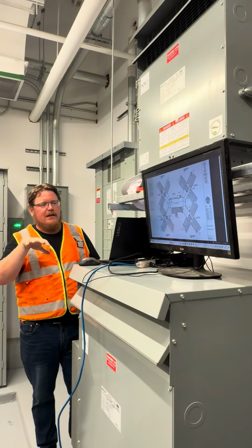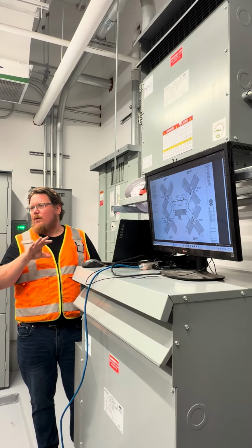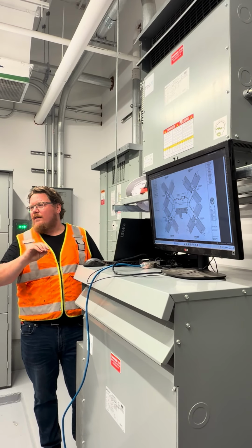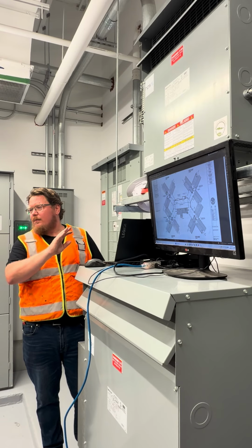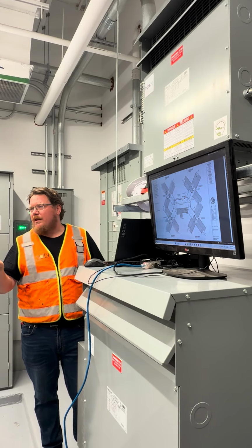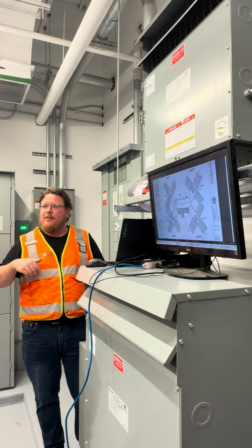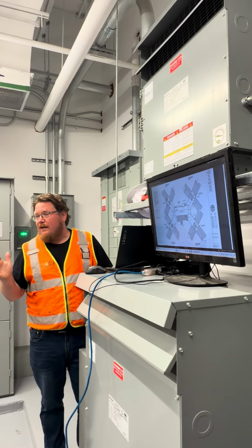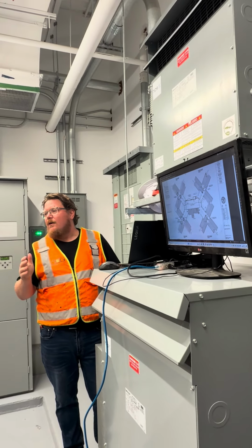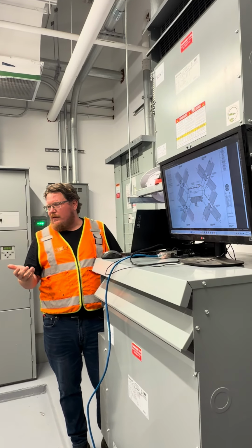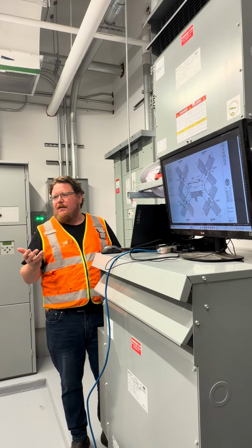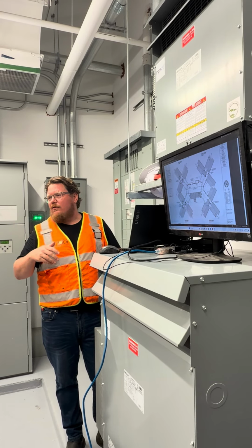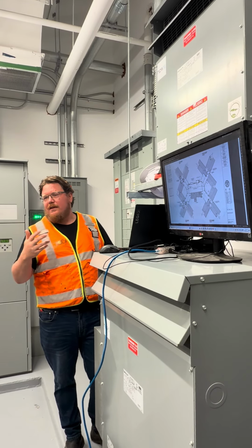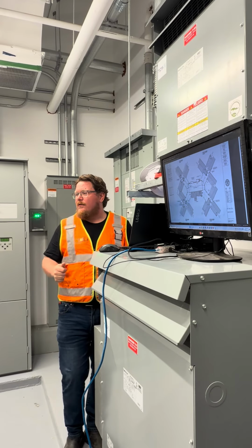In the SolarEdge software, which is the inverter manufacturer, we can set up a performance model — a prediction of what the system should do. If there's a big variance, you'll get alerts saying the system's not producing, or if there are issues with the inverter or equipment, it'll generate an alarm that sends an email to whoever you want to notify.